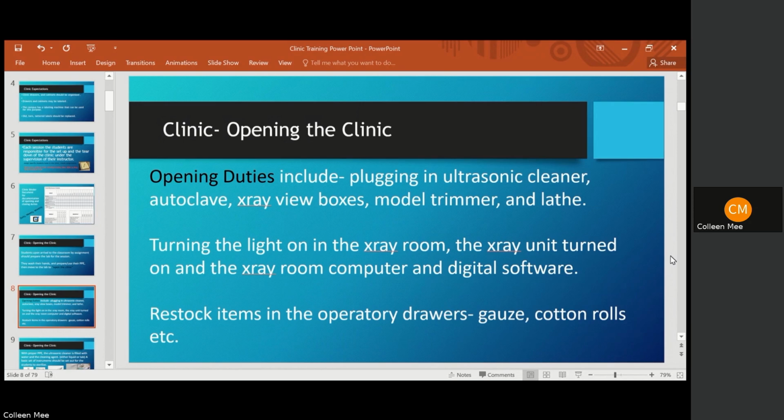Let's talk about your autoclave for a moment. Monthly cleaning is important. We certainly don't use our autoclave like a dental office. We're not sterilizing 8, 10, 12 hours a day. So it doesn't get grimy like most do in a real office, but they do need to be cleaned because we are using them a couple of times a day. Use the Omni Cleaner, follow the directions on the label, use distilled water, which by the way we buy with petty cash money. Buy at your local Walgreens, Walmart, some store like that.